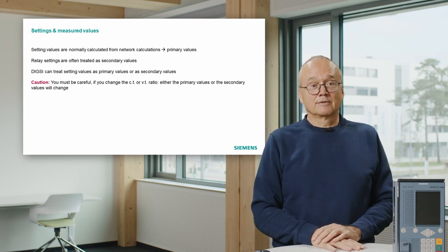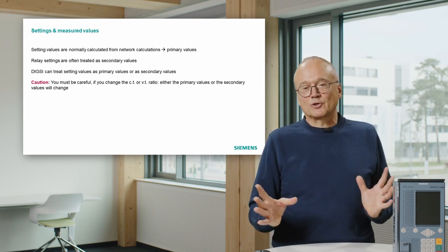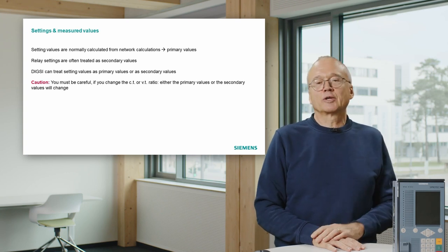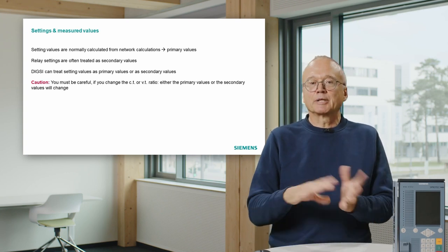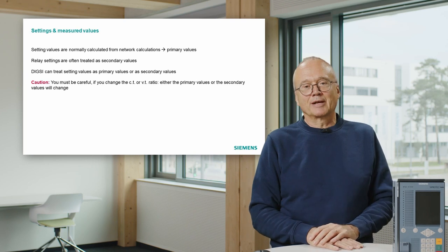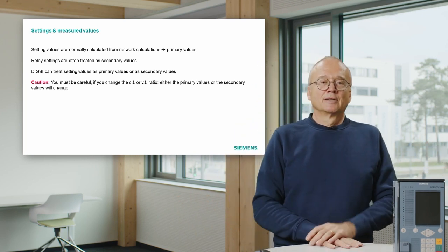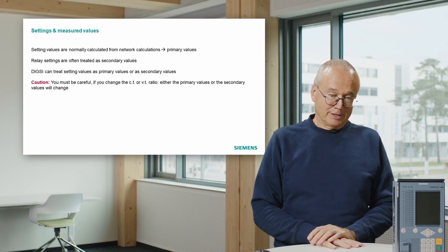And I had a lot of occurrences where something went wrong in the protection, and the end of the story was that people mixed up between primary and secondary values. It is basically trivial, but sometimes problems happen at that point.